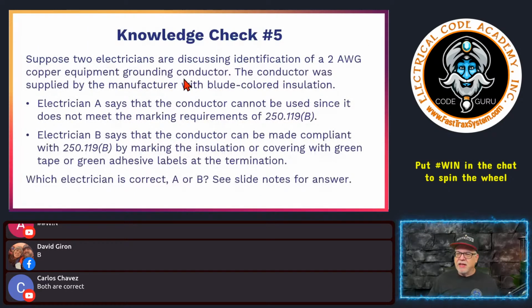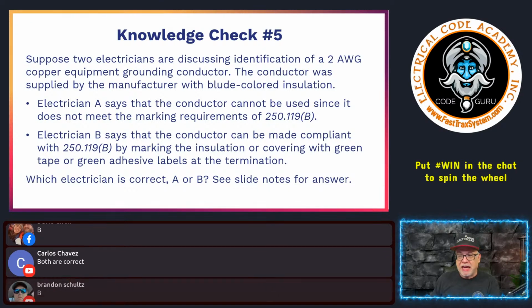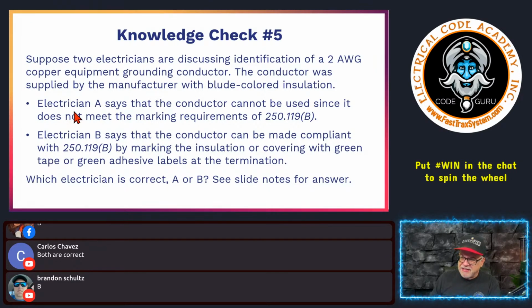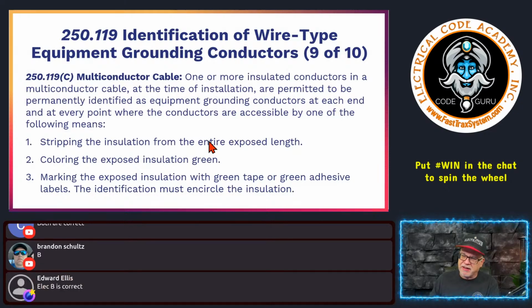So who is correct here? Y'all know the answer. No, they're not both correct. If it was a cable, you'd be able to do it no matter what the size is. If it's in a raceway, and we're not talking about neutrals, we're talking about equipment grounds, if it is 4 and larger, what we just saw says that it can be re-identified, right? So I could take that blue and re-identify it at termination with green tape, and it would be perfectly okay to do that. Guys, that's just what we just read back here.